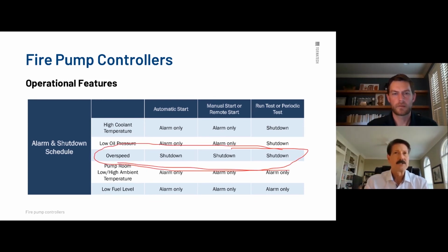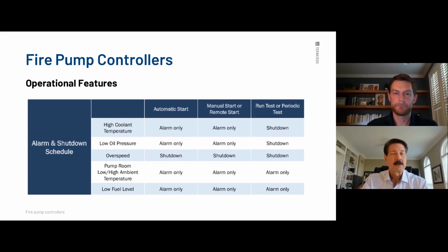Overspeed is that option, just like in the electric where you have locked rotor current, 600%, 8 to 20 seconds. There's more potential damage there by not tripping it offline. The same thing when you have a runaway engine, what happens? You're going to have overspeed. Obviously, you could potentially exceed the mechanical parameters of the motor and cause it to blow something. But you're going to overpressurize the system and your piping's probably not going to hold.